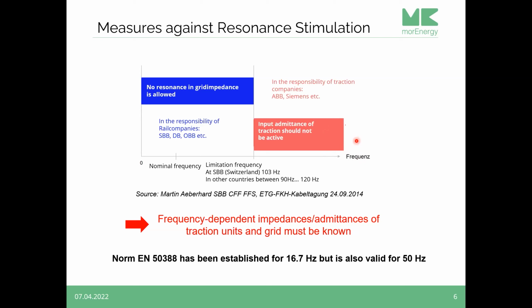So there are two things that have to be done within this compatibility test: on the one hand, to determine the grid impedance of the grid infrastructure, and to determine the admittance of the traction. Up to now, there's no possibility to measure the grid impedance, so in the norm it is also proposed to calculate the grid impedance. But this is very complex, and I'll come to it later, that we can also do it with our technology. On the other hand, we need to measure the admittance of the traction unit.